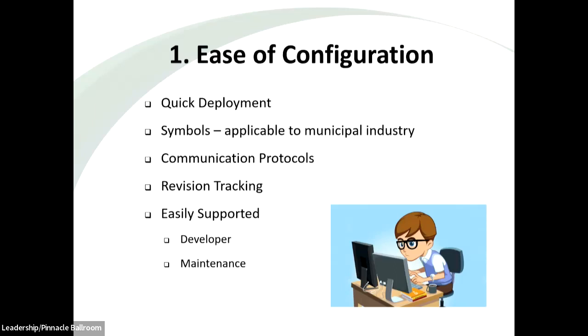Revision tracking is a feature that some SCADA systems have, where if you do development and make changes, you can revert back if your changes are not the way you expected. It's like history tracking in things like Word or Excel, where you can go back to previous versions when you saved your document. SCADA systems have that feature nowadays, and it can be really valuable—for example, for backups. If you get hacked, or if something was broken, you can simply revert back very quickly to the version of known software you know worked and deploy that again.